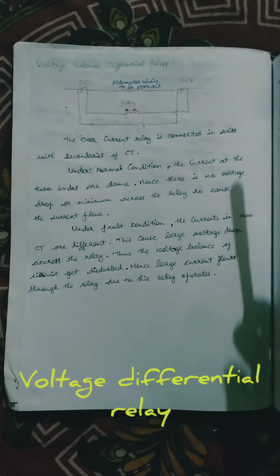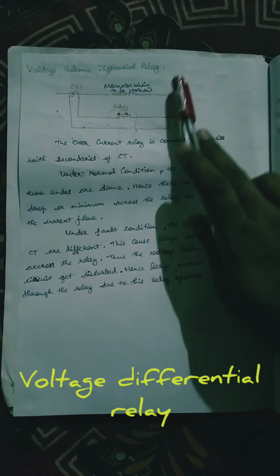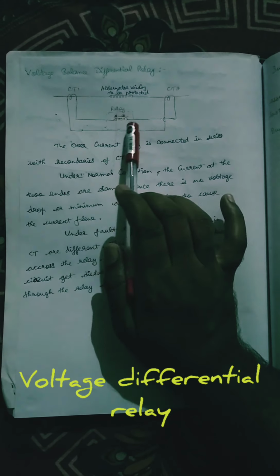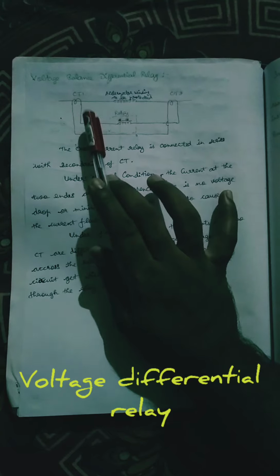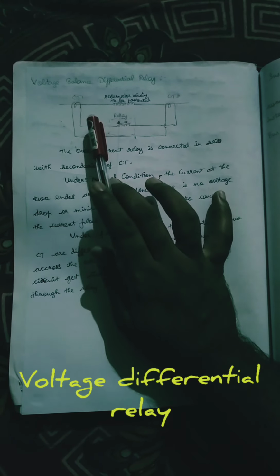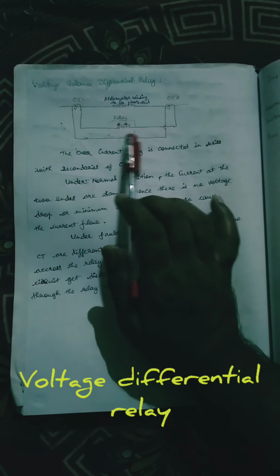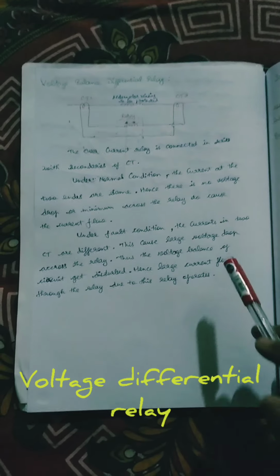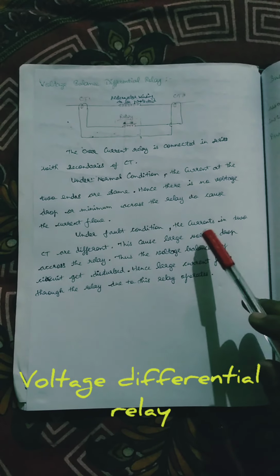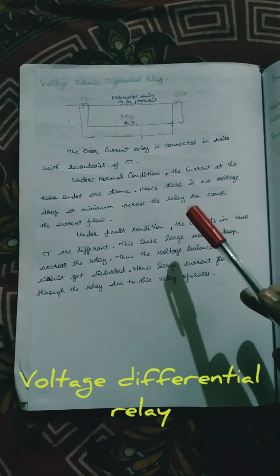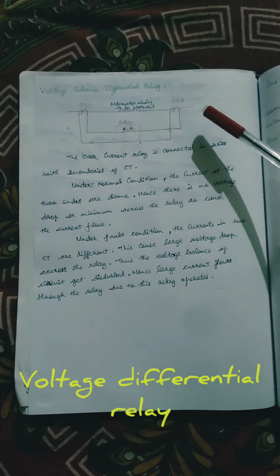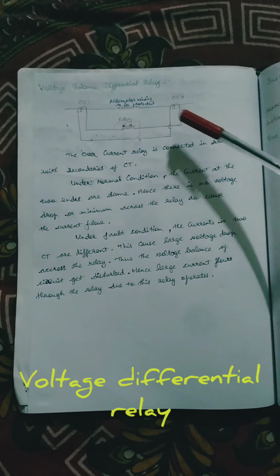Next is the voltage balance differential relay. Here a relay coil is connected in series with CT1 and CT2, the current transformers. The overcurrent relay is connected in series with the secondaries of the CTs. Under a normal condition, the current at the two ends will be the same.